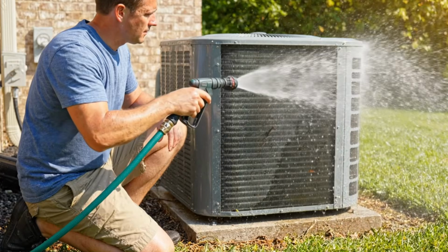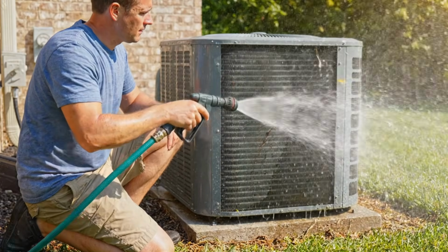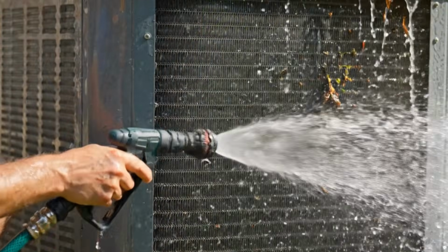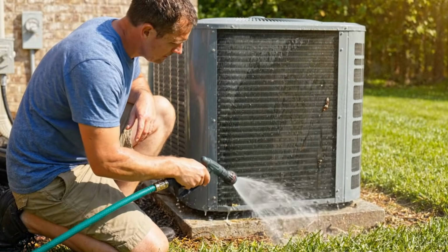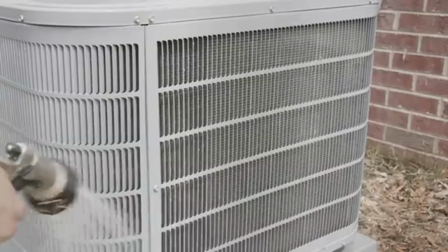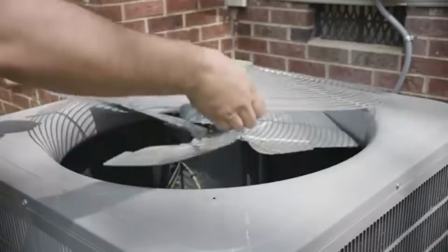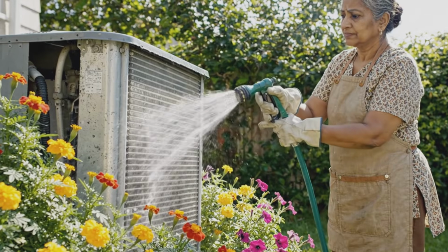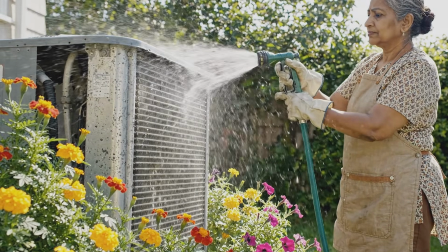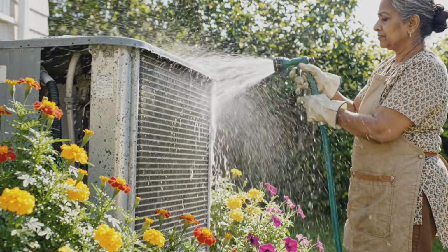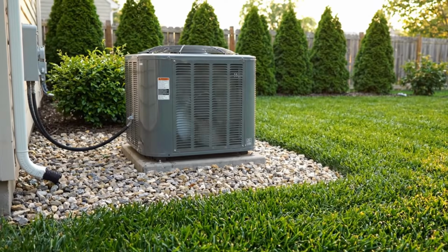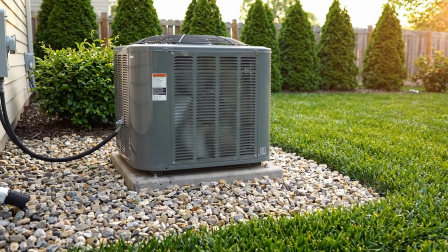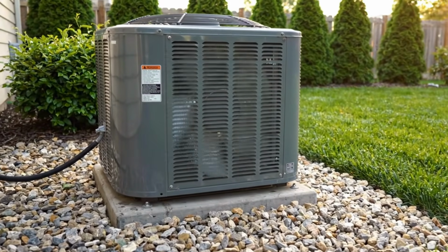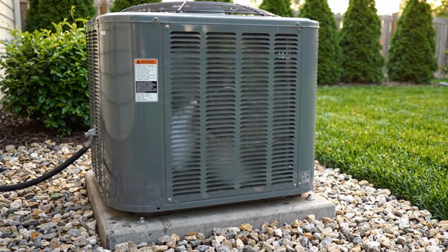Once a year, ideally in the spring before cooling season, spray the coil down with a gentle garden hose from the inside out. You're trying to push debris outward, not compact it inward. Keep landscaping at least 18 to 24 inches away from all sides, and check that the unit is level. They can settle over time, and a tilted compressor doesn't oil properly. 20 minutes once a year.